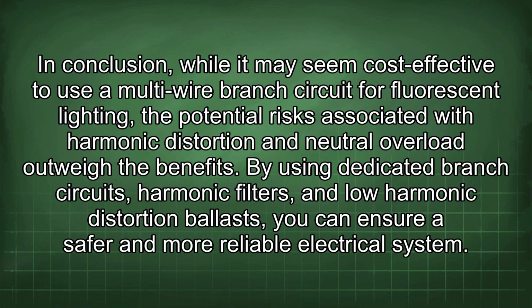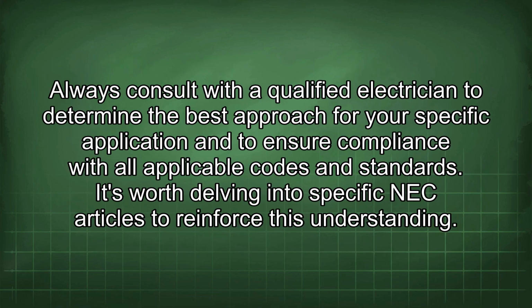In conclusion, while it may seem cost-effective to use a multi-wire branch circuit for fluorescent lighting, the potential risks associated with harmonic distortion and neutral overload outweigh the benefits. By using dedicated branch circuits, harmonic filters, and low harmonic distortion ballasts, you can ensure a safer and more reliable electrical system. Always consult with a qualified electrician to determine the best approach for your specific application and to ensure compliance with all applicable codes and standards.